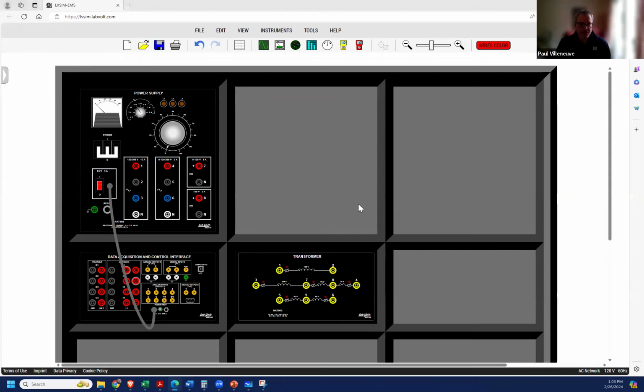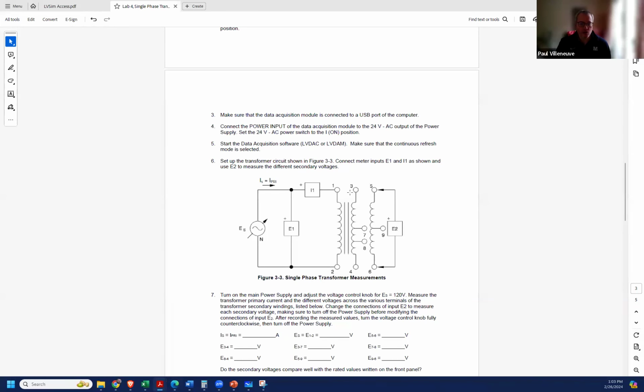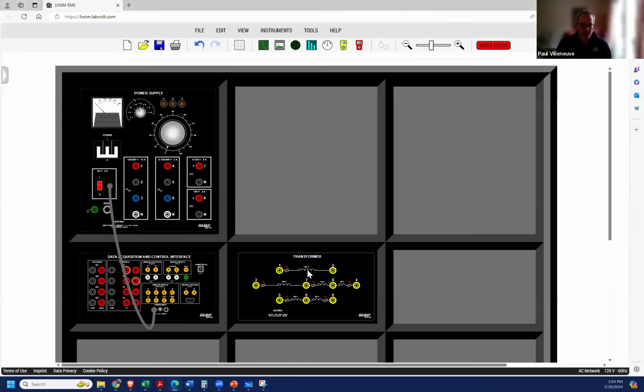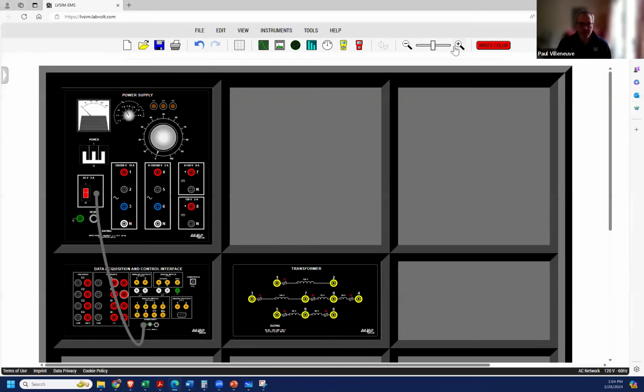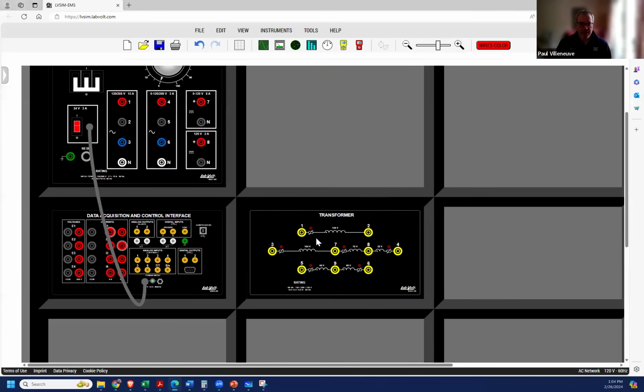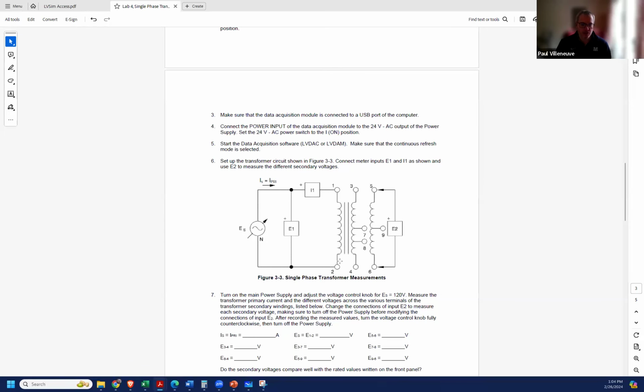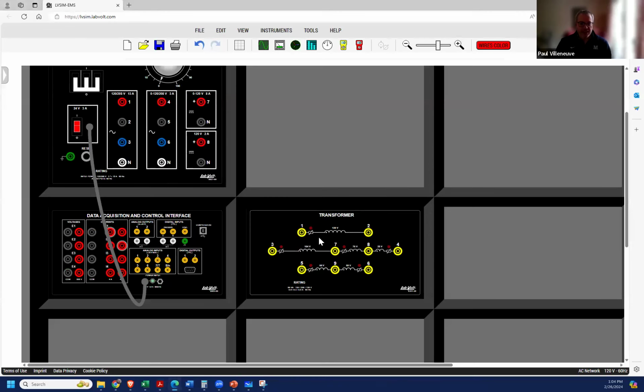Now, going back to the circuit, what terminals or numbers do we need, keeping in mind we want to apply the rated voltage of this single phase transformer? If you go back to the transformer, kind of hard to see, let me zoom in a bit. You can see that across terminals 1 and 2, it's nominally rated for 120 volts.